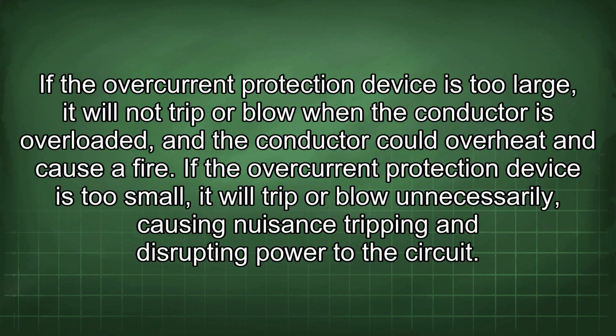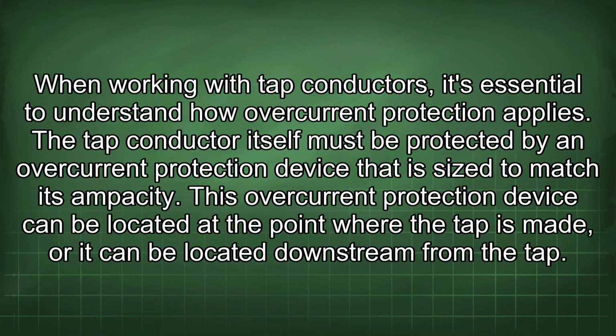protecting. If the overcurrent protection device is too large, it will not trip or blow when the conductor is overloaded, and the conductor could overheat and cause a fire. If the overcurrent protection device is too small, it will trip or blow unnecessarily, causing nuisance tripping and disrupting power to the circuit. When working with tap conductors, it's essential to understand how overcurrent protection applies. The tap conductor itself must be protected by an overcurrent protection device that is sized to match its ampacity.